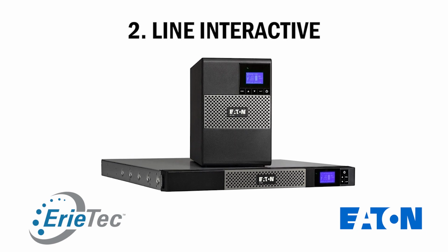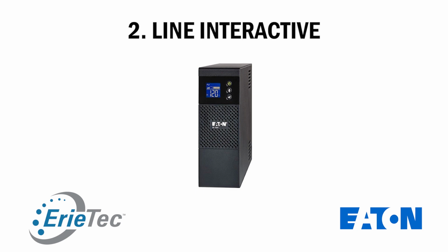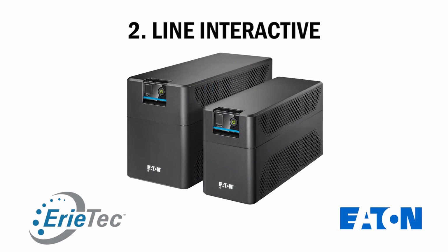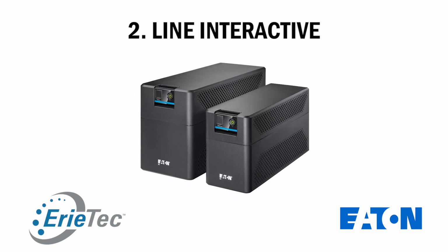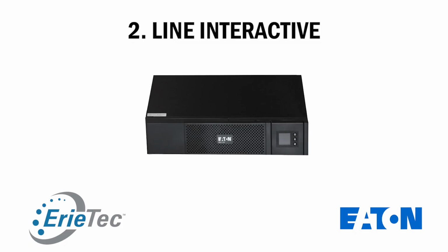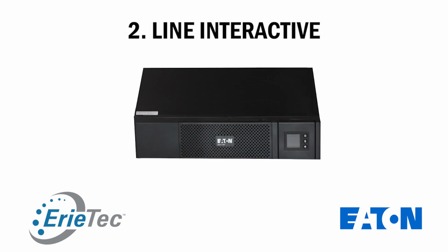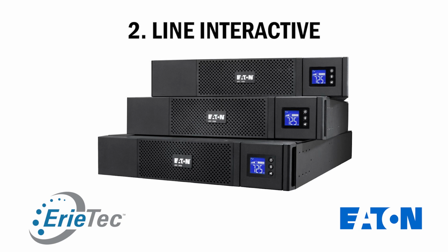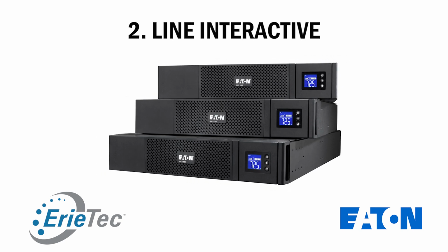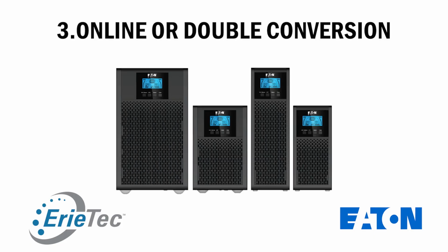A line interactive UPS is the next type. It provides more power quality control than a standby. Under normal circumstances, again, it will allow the utility to pass through the UPS directly to the load. It has surge protection, and it has an inverter that can actually act as a buck or a boost to the incoming utility signal. So in addition to power outages and slight overvoltages and undervoltages, it can also do longer term sags and surges because the inverter can actually alter the output waveform and allow it to run while the incoming power is not perfect. Then when the utility goes out, the same thing happens as with the standby UPS. The contactor opens, and the inverter takes the full load being supplied by the batteries. And when the power comes back on, the contactor closes, the inverter backs off, and the small rectifier inside will recharge the batteries.